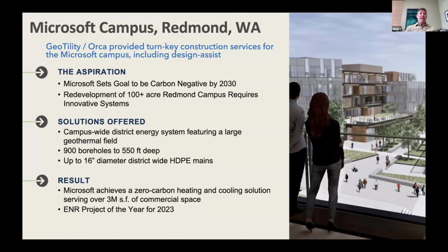As part of that, they decided on a geo system because, frankly, if you're trying to scale a zero-carbon system — think about those thermal energy networks — geo is really the best technology to accomplish that. Going with 2,000 to 3,000 ton air source heat pumps is really challenging, hard to find space for. This system happens to be a hybrid, with some electric boilers for peak heating loads, but it's primarily fed by the geo system.